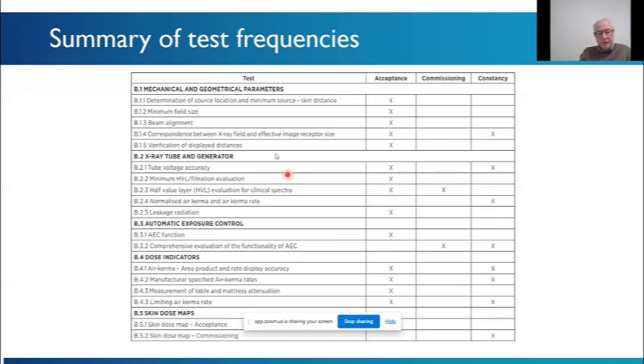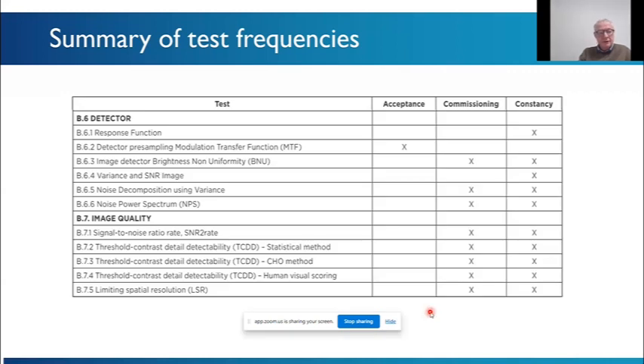We have a summary of the tests at the beginning of the protocol, and you can see the mechanical, X-ray tube, generator and AEC tests, which are very well defined and have quite an IEC flavor. These are more like acceptance tests, where you check how the system has been installed, because they are well defined and there will be an IEC method for doing it, which we follow quite often. They're not really commissioning. Commissioning is more to do with how the system is performing with respect to its clinical performance, and then we can do some constancy tests with these. So it's more like an acceptance test, seeing how the system has been installed by the manufacturer or the vendor. We then go on to the other tests, which are the X-ray detector and the image quality.